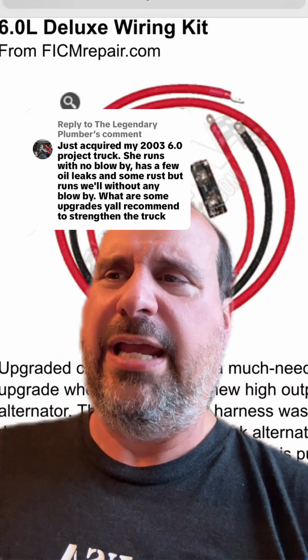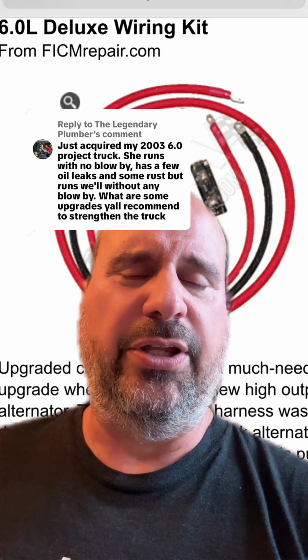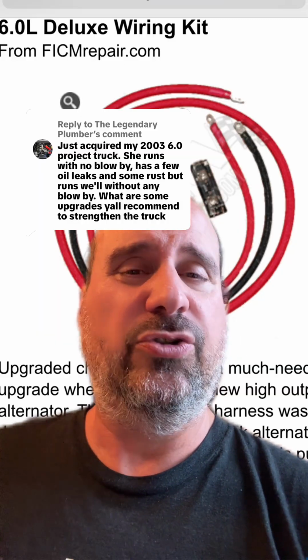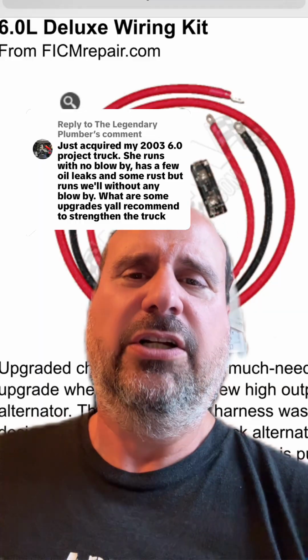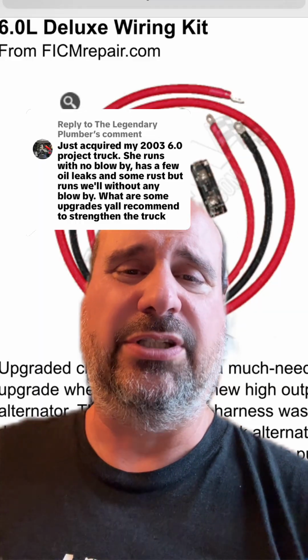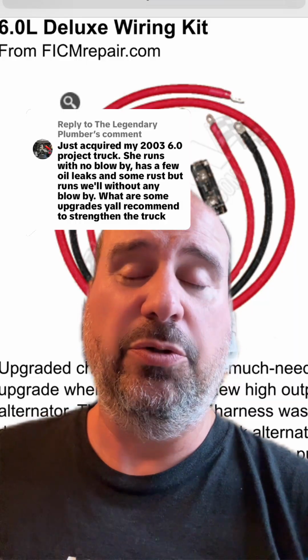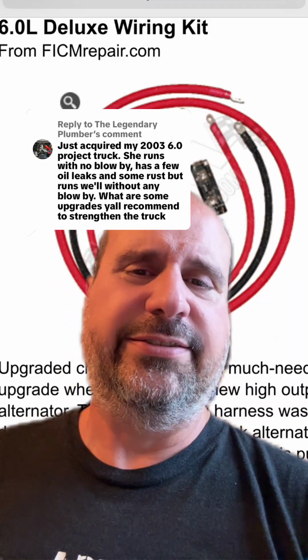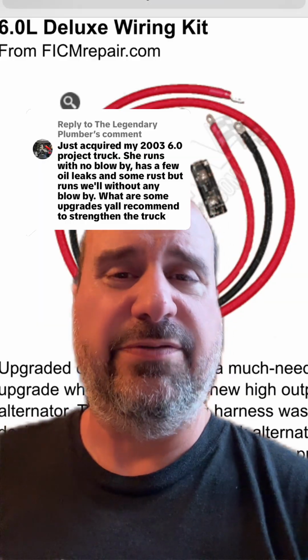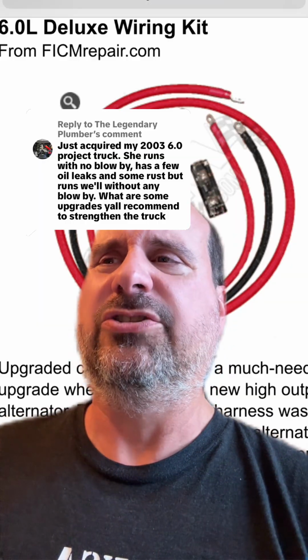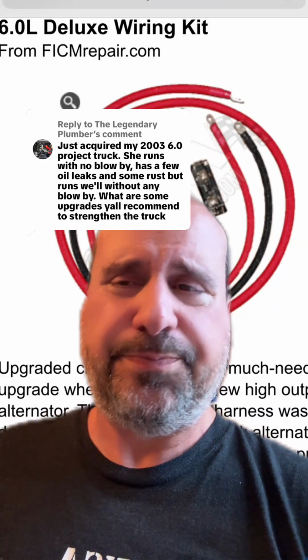Our cable kit includes a cable that you run over the top of it, a 4/0 cable at 211,000 circular mils. So you end up with a little more than 4 times the copper between the batteries, which is a huge win. But recognize that electrons travel from the negative to the positive, not from the positive to the negative. So without adding another ground, that bigger cable isn't going to do very much for you.